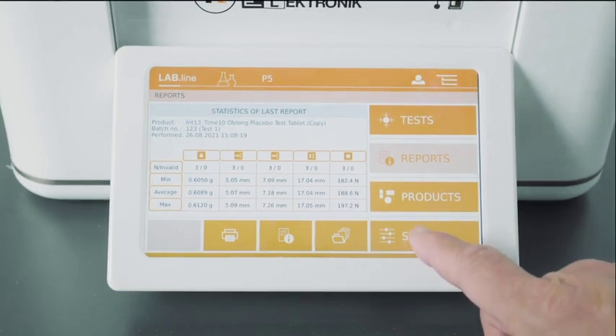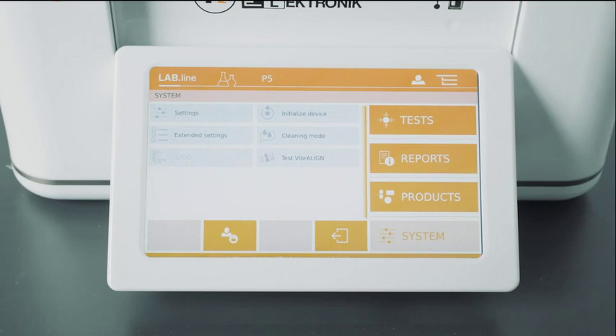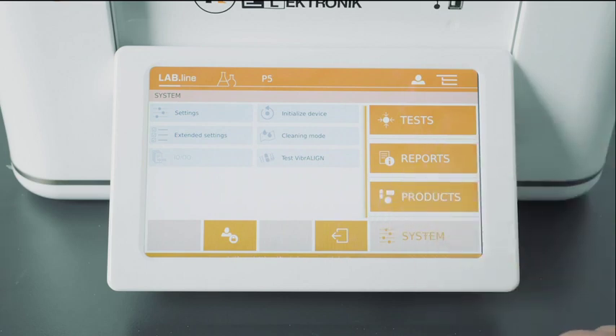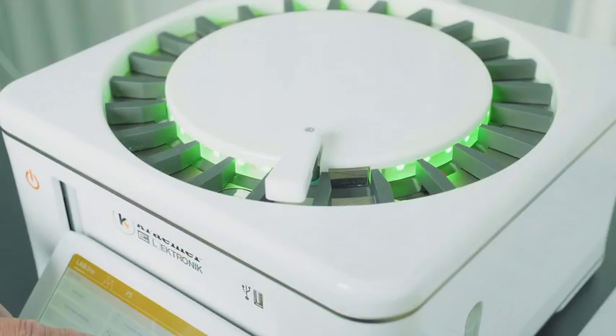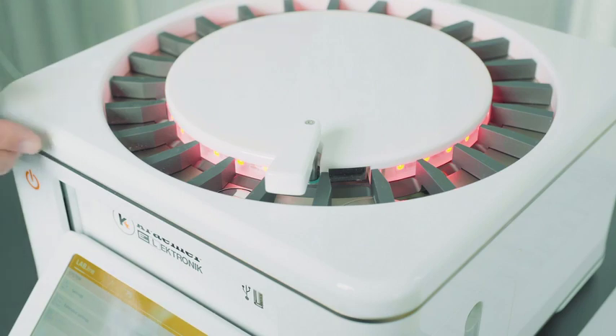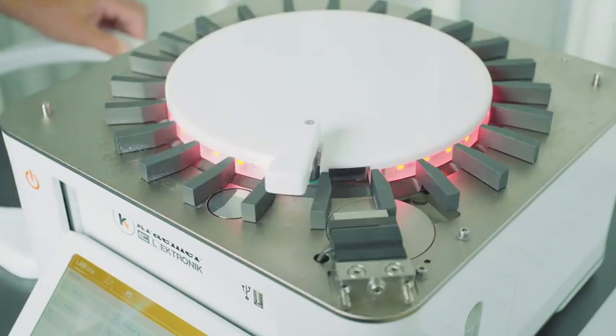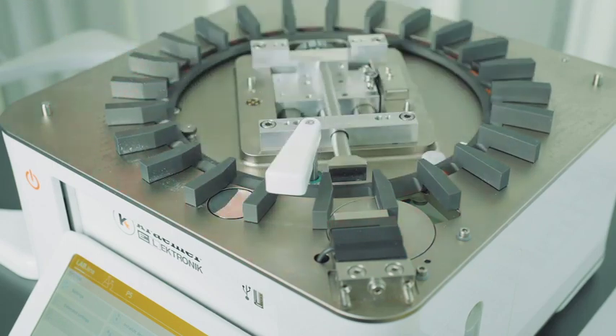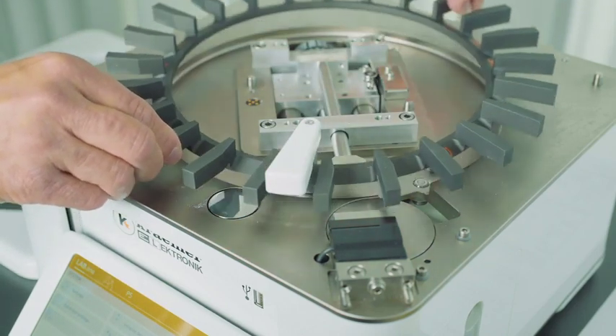Then we have here a menu system where we have settings and extended settings to parameterize and configure the system. We have an initialization button to initialize, reset the whole tester. We have a cleaning mode. By selecting the cleaning mode, the thickness gauge moves up and the hardness tester backwards to make it easier to remove the different components, such as the cover and as well the star wheel.